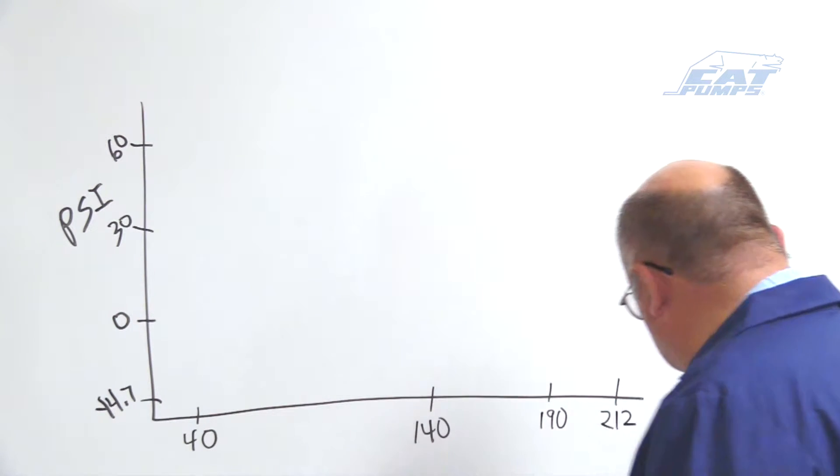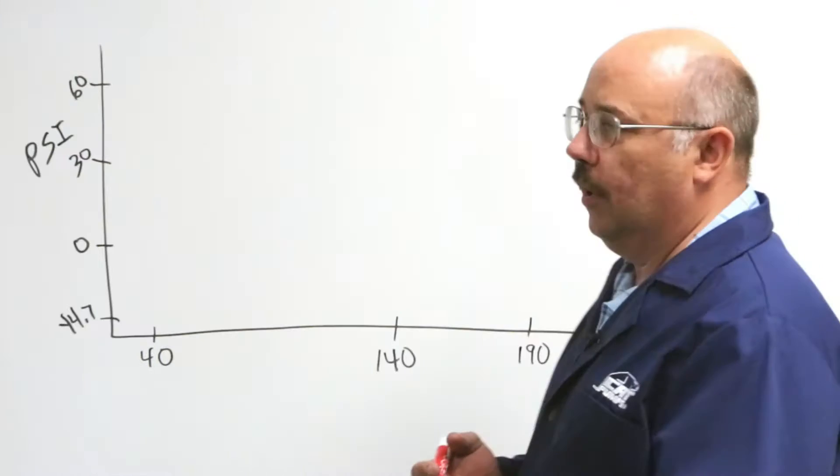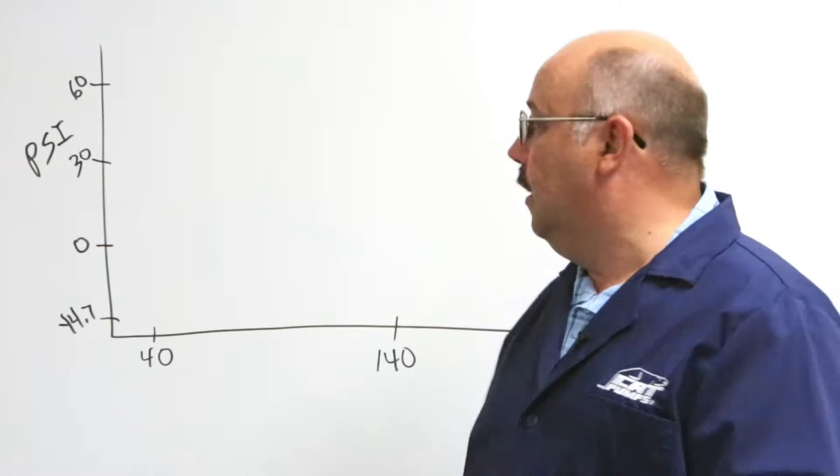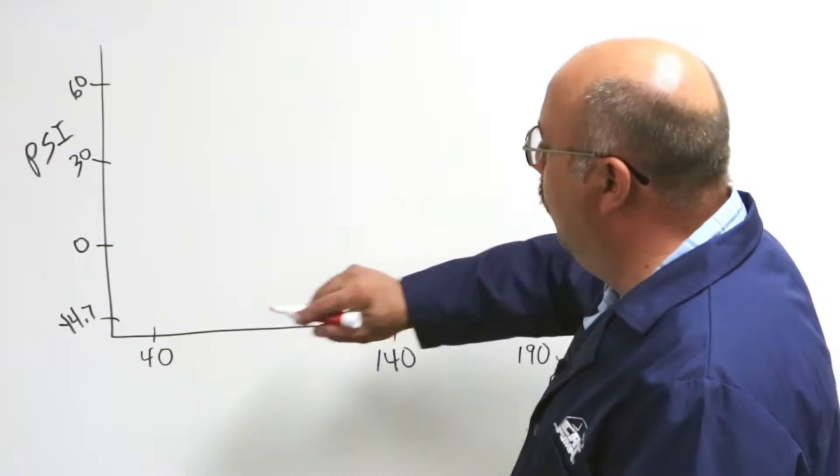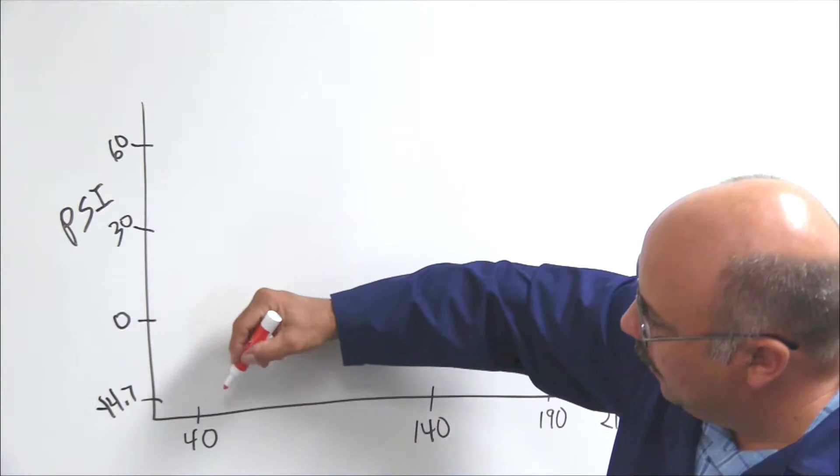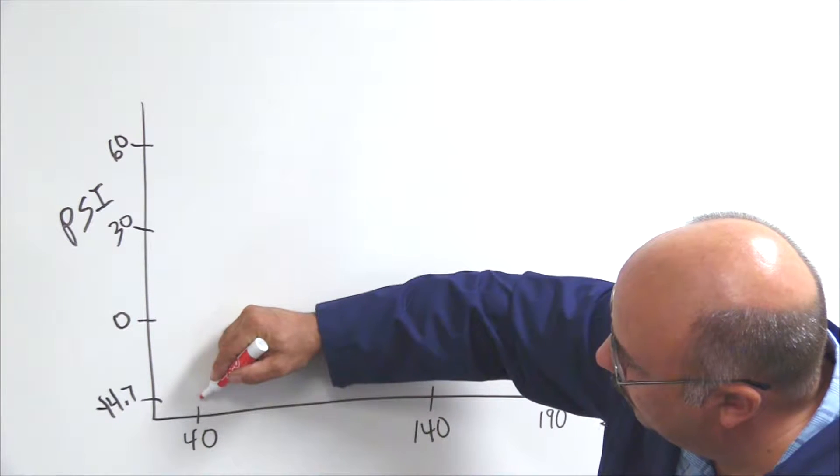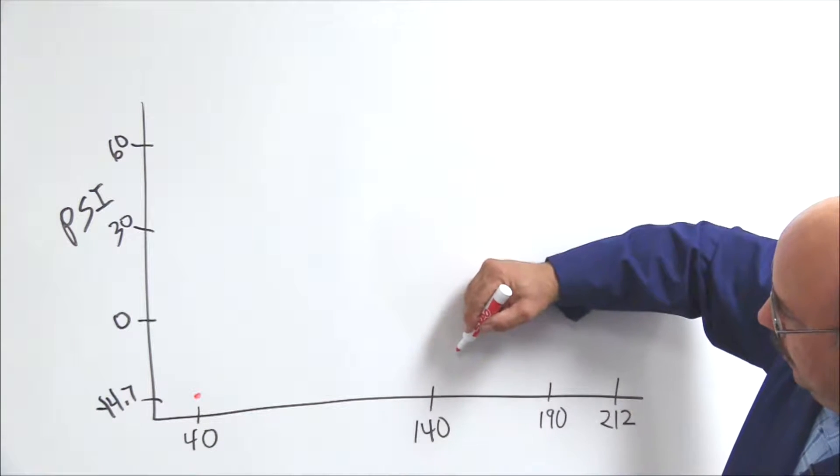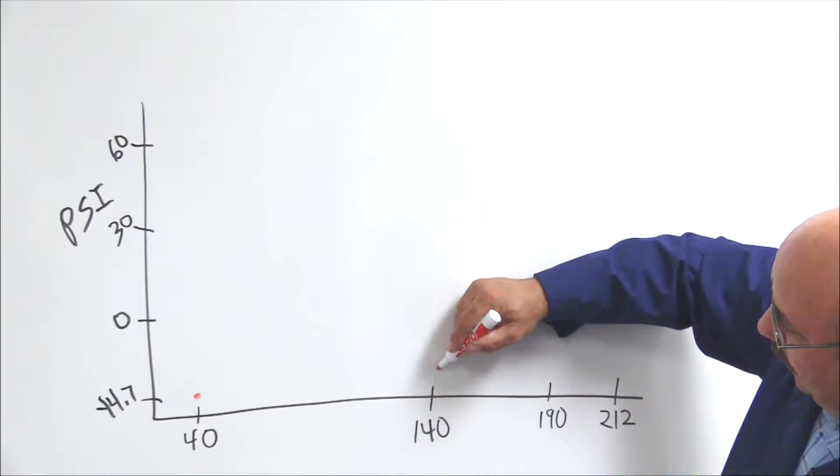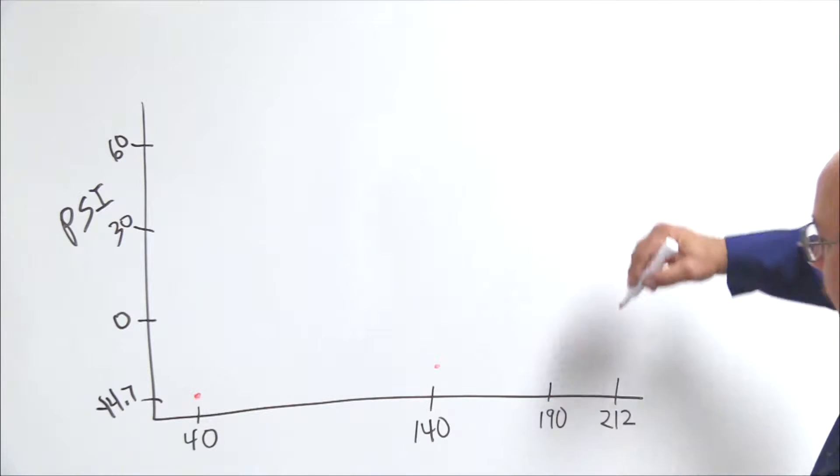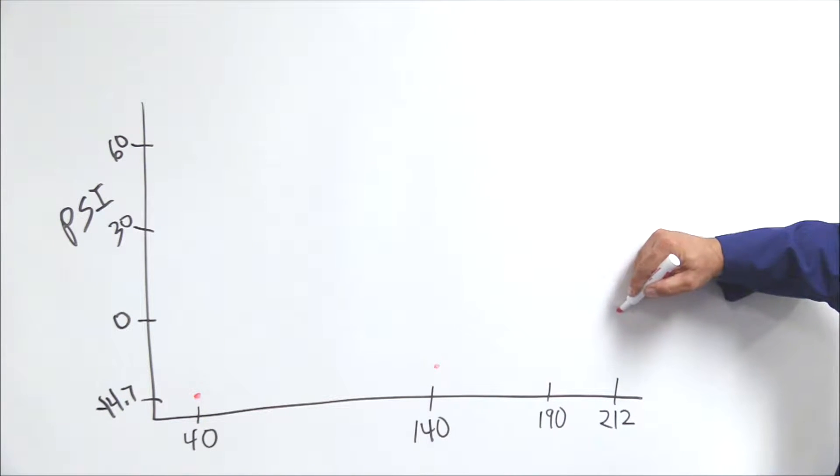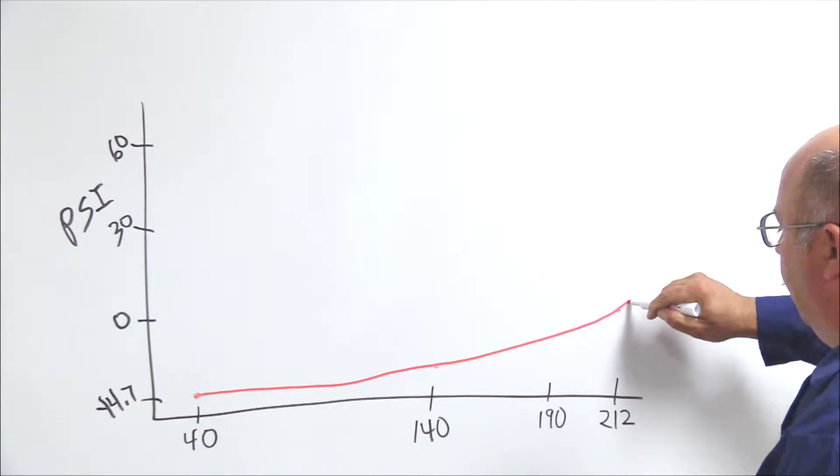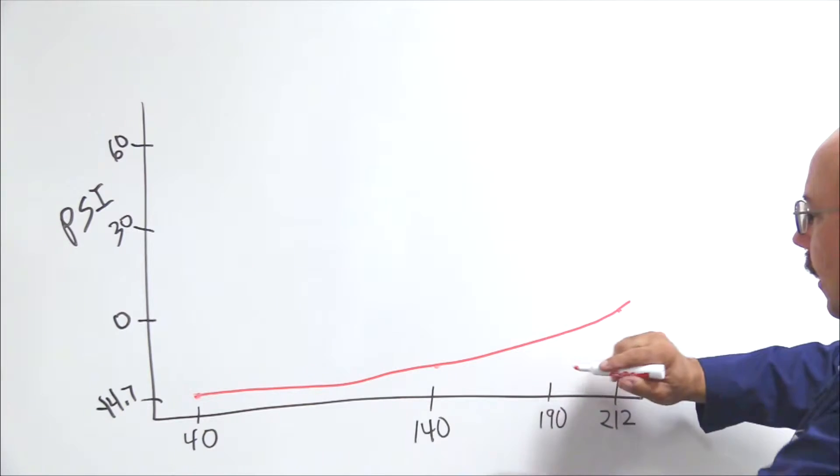And when we start talking about water, water as a liquid is dependent upon its temperature and pressure. So we have to look at both characteristics when we're talking about water. Well down at 40 degrees it's still a liquid way down at almost a perfect vacuum. At 140 it's around minus 10 psi is where the vapor line is. And at 212 it's at 0. So I'm going to draw this line. And everything below the line is vapor.